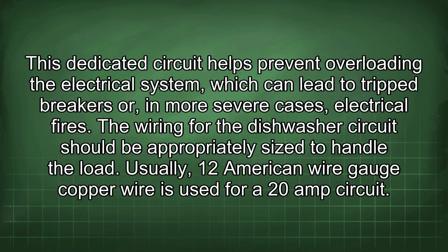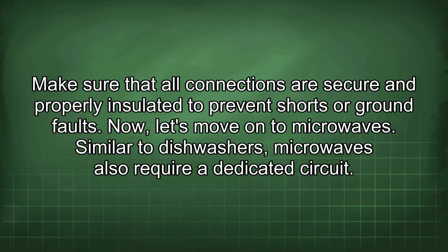This dedicated circuit helps prevent overloading the electrical system, which can lead to tripped breakers or, in more severe cases, electrical fires. The wiring for the dishwasher circuit should be appropriately sized to handle the load. Usually, 12 American wire gauge copper wire is used for a 20-amp circuit. Make sure that all connections are secure and properly insulated to prevent shorts or ground faults.